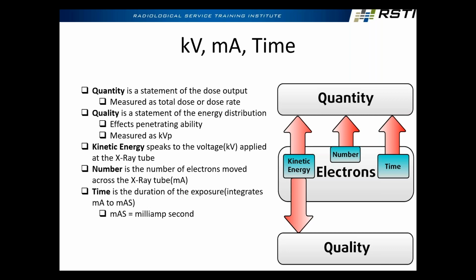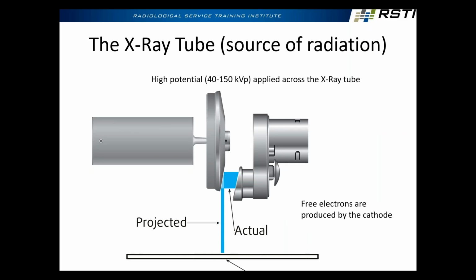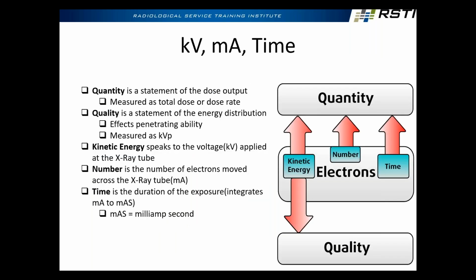All right. So when we talk about quality, another way to think of beam quality is beam hardness or the penetrating ability. We want it to be penetrating enough that it gives us what we want to see, but not so penetrating that we start losing information. All of this is controlled by our little friends, the electrons. These are the electrons that are going to be generated right here at the cathode. When we heat up that filament in the cathode, that 4 to 5.5 amp range, that takes us into the realm of what's known as thermionic emission.